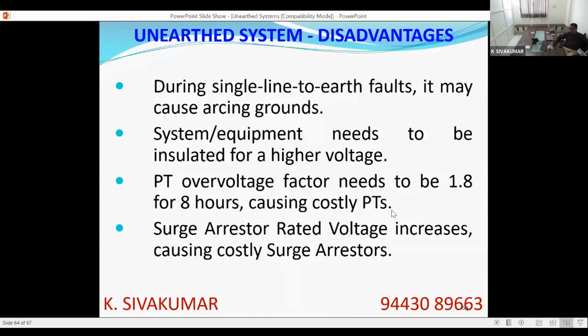Similarly, if you see the surge arrestor rated voltage calculations, it depends upon something called the ground fault factor. The ground fault factor is 0.8 for solidly grounded systems, and it will vary from 0.8 to 1.732, as high as 1.732 for unearthed systems. So definitely for an unearthed system, if you want to use a surge arrestor, you have to use a higher rated voltage arrestor, which will make the arrestor bulky and costly also. So these are some of the disadvantages of the unearthed system.